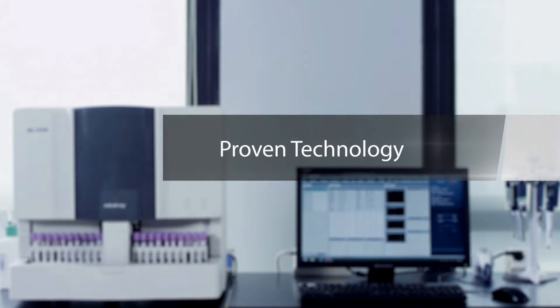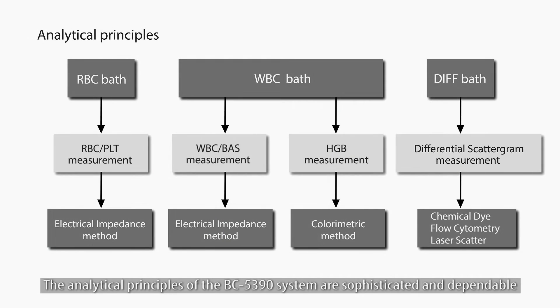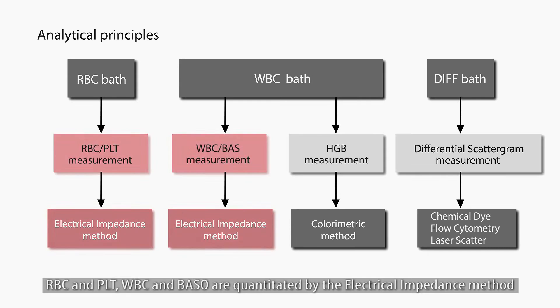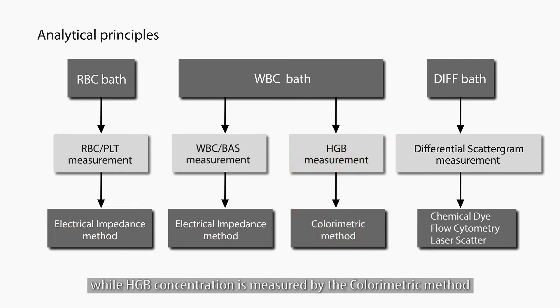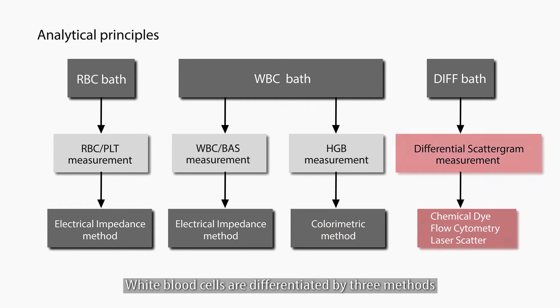Proven technology. The analytical principles of the BC5390 system are sophisticated and dependable. RBC and PLT, WBC and BASO are quantitated by the electrical impedance method, while HGB concentration is measured by the colorimetric method. White blood cells are differentiated by three methods: chemical dye, flow cytometry, and laser scatter.